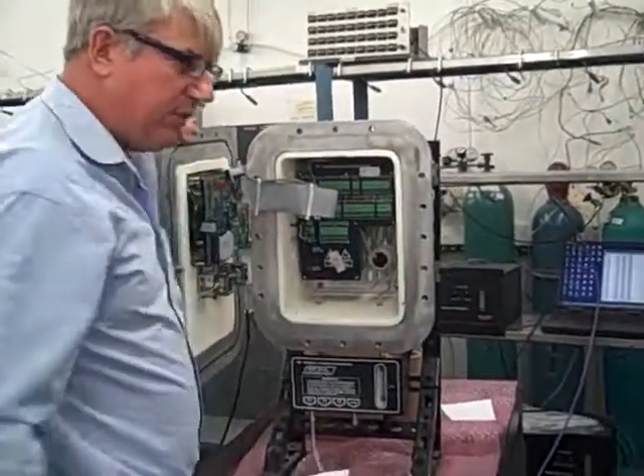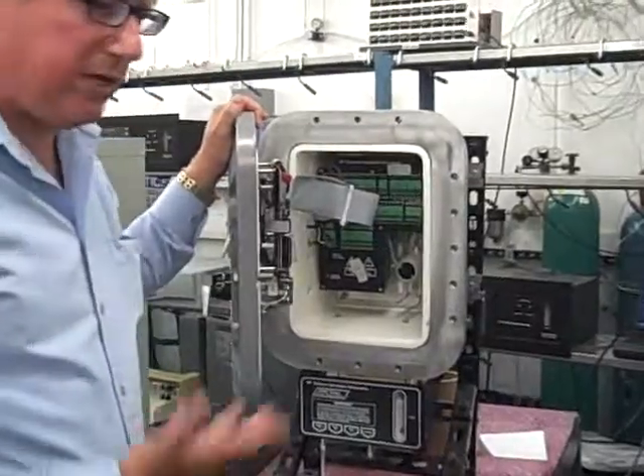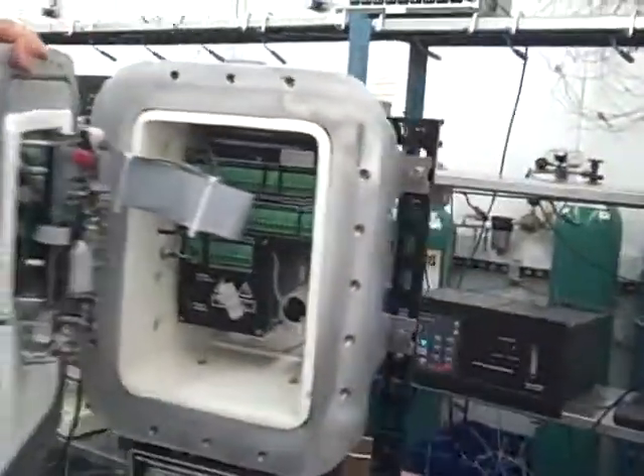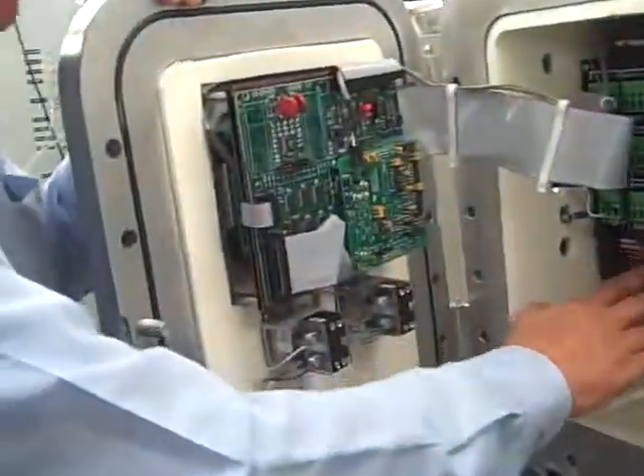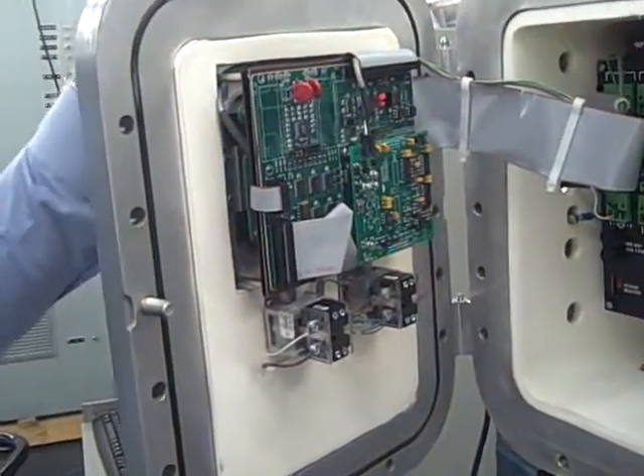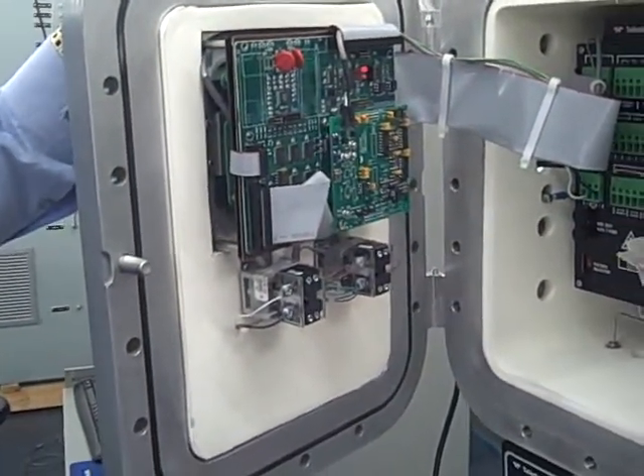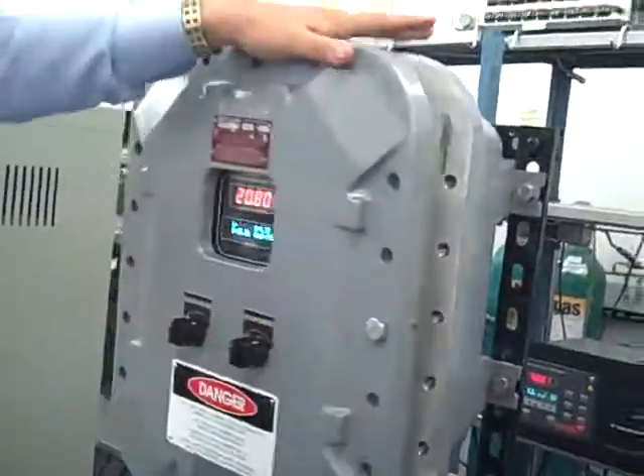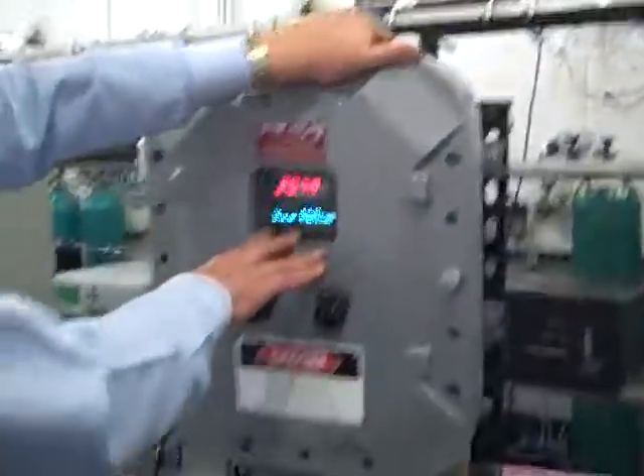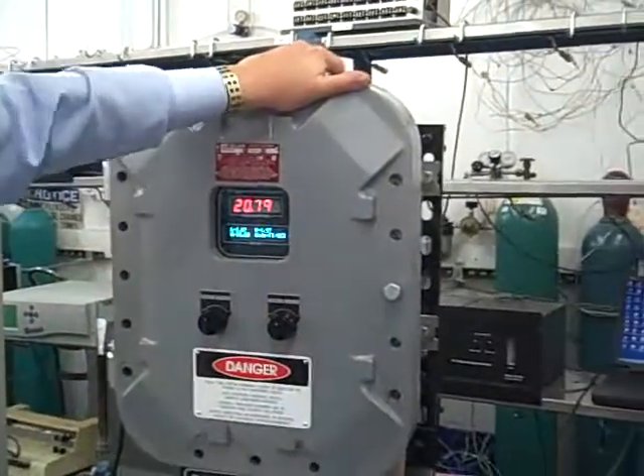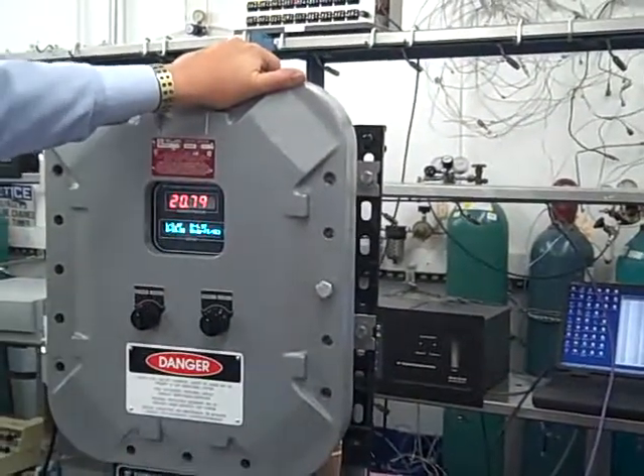These boards will last typically many, many years and give good service. Occasionally there will be a circuit board malfunction after many years. The thing most likely to malfunction in the unit would be the power supply. You can tell if the power supply is bad by going through the diagnostic features, or the unit won't power up. If the unit won't turn on at all and you have AC power, it's probably a power supply.